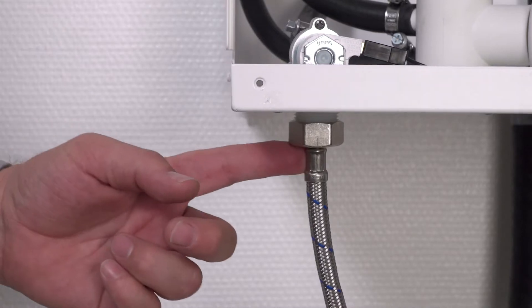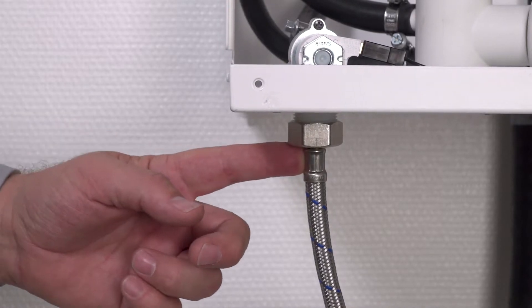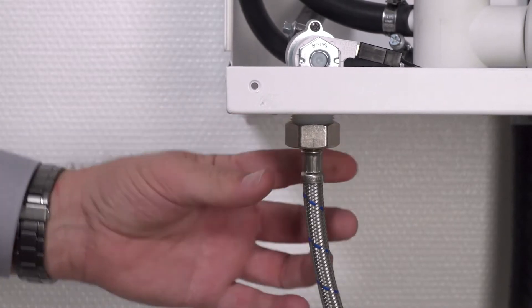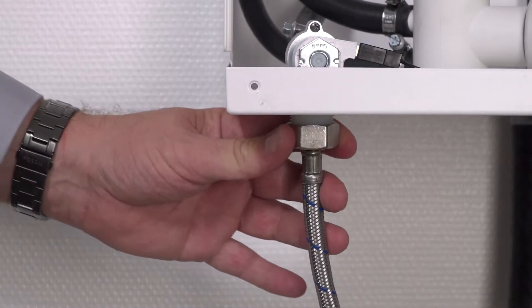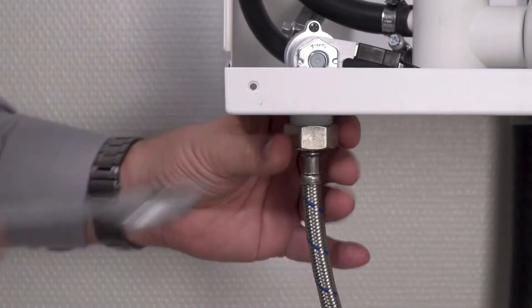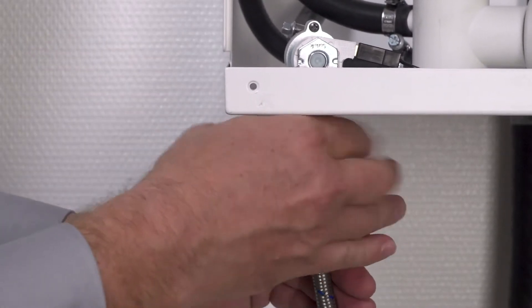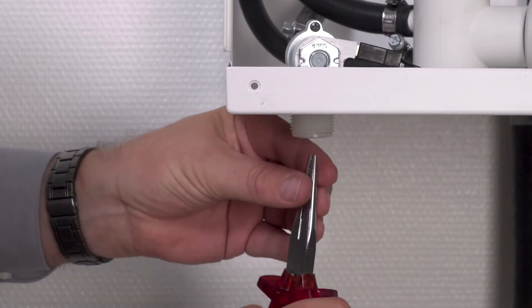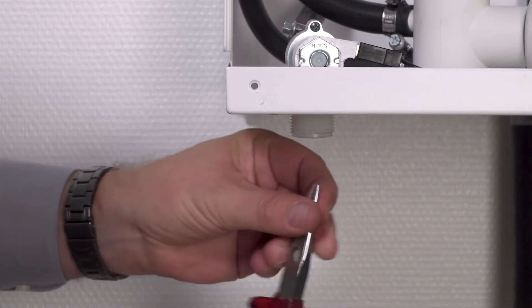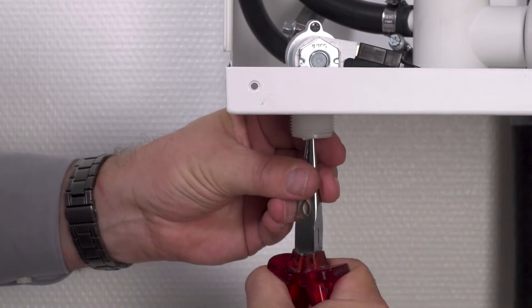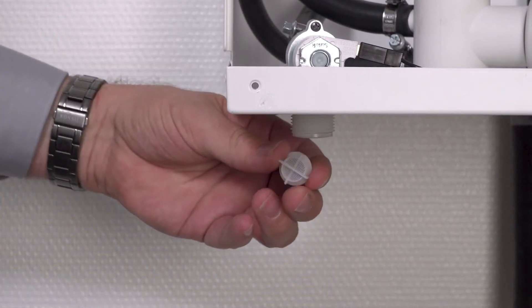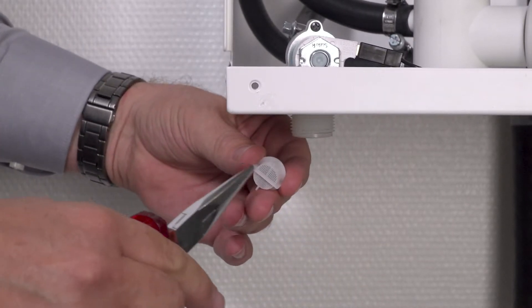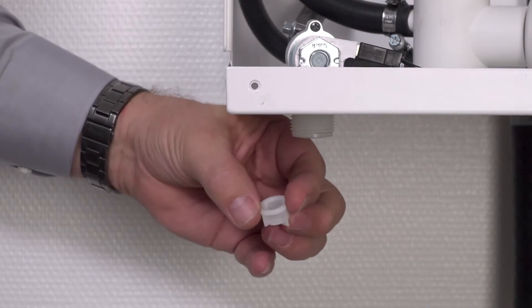A further maintenance step is to clean the sieve in the solenoid valve. To do this, I loosened the nut found underneath the unit and simply pull the sieve out of the guide with a pair of pointed or flat-nosed pliers. The sieve can be cleaned under running water and reinserted.